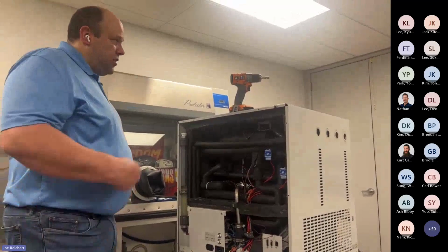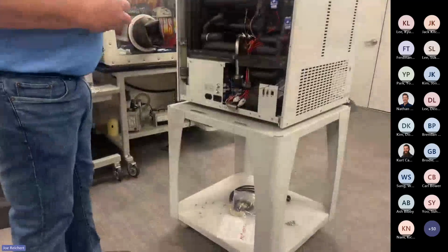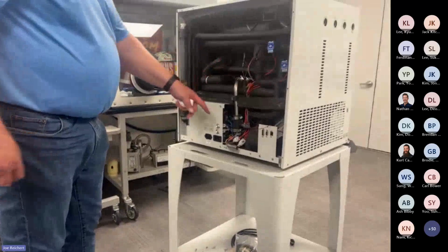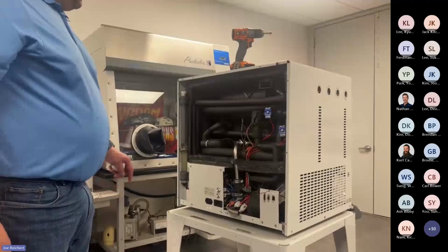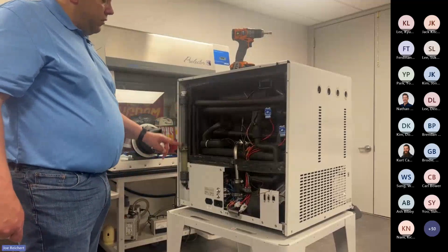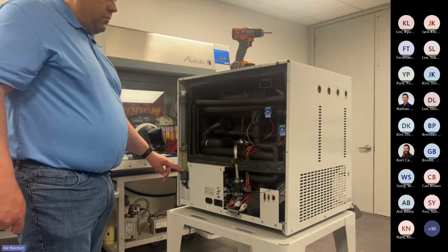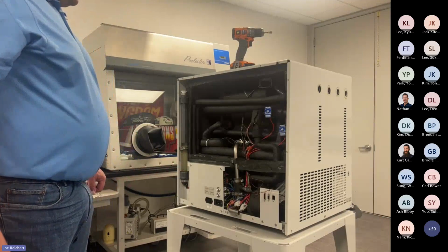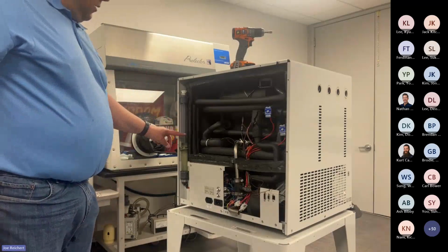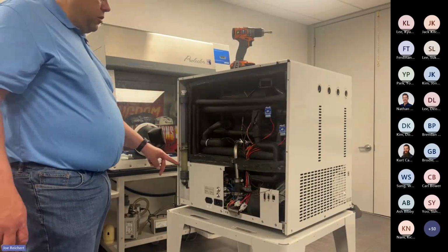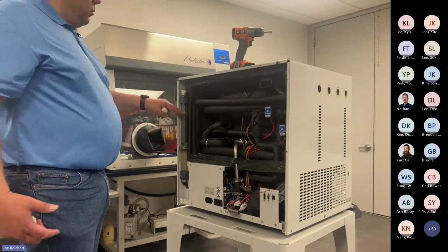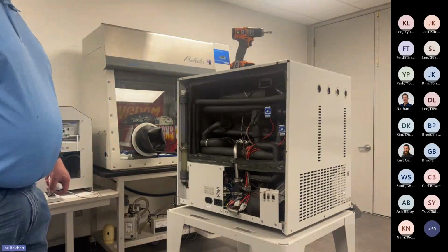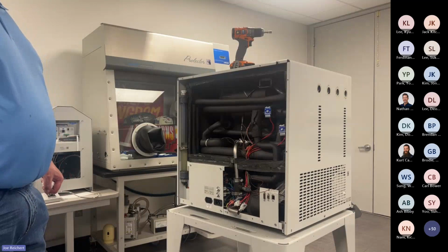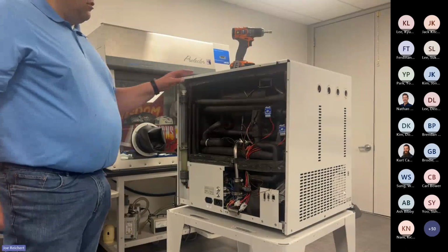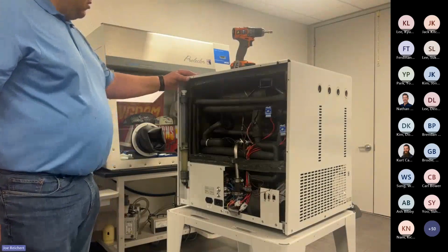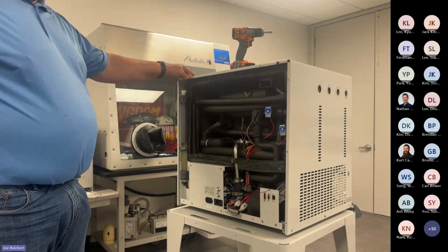If you have air in your system, air within the shelf or in your lines anywhere for the Lexol system, even back to the pump, it should have no air. But if it does, you'll know it because you'll have a much more fluctuation of the Lexol level in your tank. It might go all the way down to the bottom whenever we have air within the system. That air will compress and it'll move throughout the system, but your Lexol level will go down. And then as soon as you turn it off, the Lexol level will rise back to where it normally was. The issue with having air in the system is that you're no longer having Lexol flow, so your shelf is not going to cool like it's supposed to at that point. So that is the chance to bleed the air from the system.